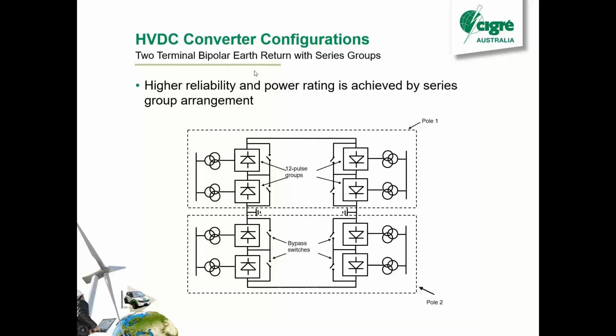Now this is for the really big HVDC bipoles. They use this configuration, so they call it series group, and that allows you to basically put 2 valve halls in series per pole, and you have these bypass switches. So it allows you to basically stack it up. So if we've got plus or minus 350 kV, if we duplicated one of the valve halls, we could get 700 at the same current. And that's basically what's being achieved here. And a lot of those big links in China use this configuration.